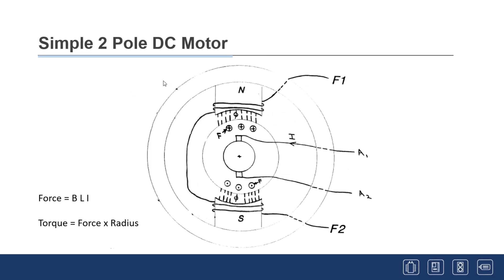A DC motor's speed is not dependent on number of poles — unlike an AC motor. Think of it like a car engine: more cylinders give more power. With a DC motor, more poles allow more flux into the armature to affect the conductors, which produces more force. With field excitation applied, flux flows through the air gap, through the armature, and out the other side around the frame. Conductors in the armature run lengthwise and connect to a commutator — that copper cylinder with insulated segments — and brushes on the commutator bring current in from the drive.